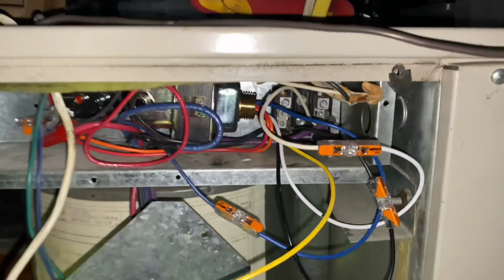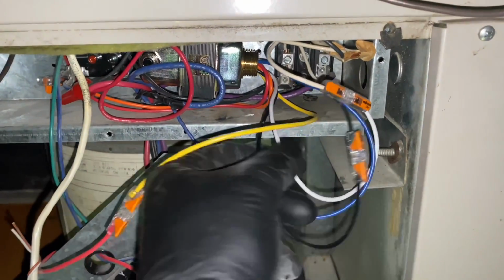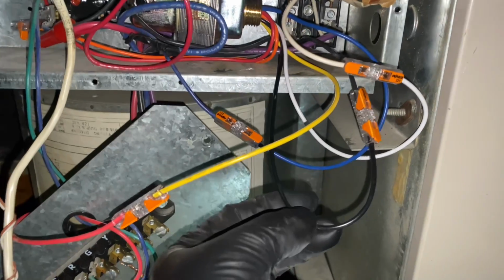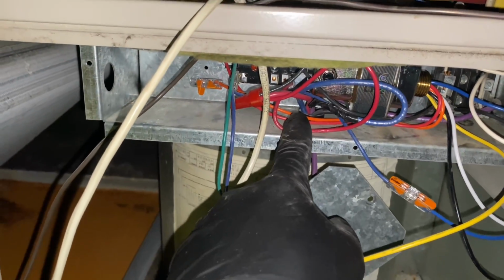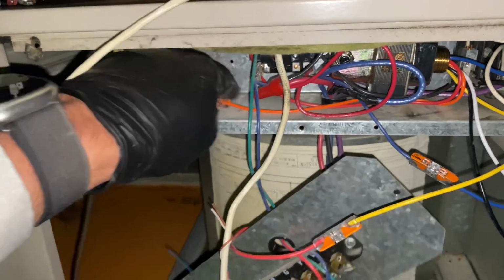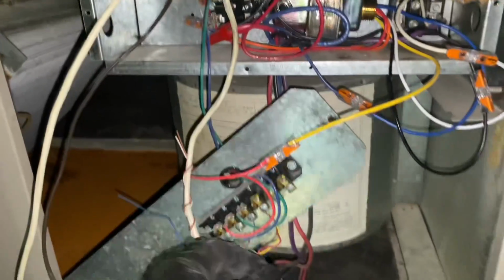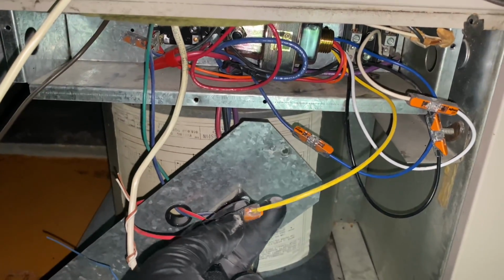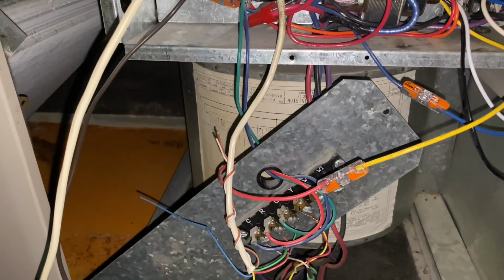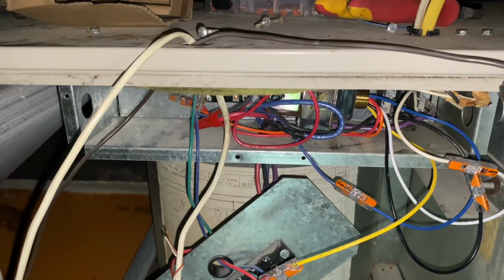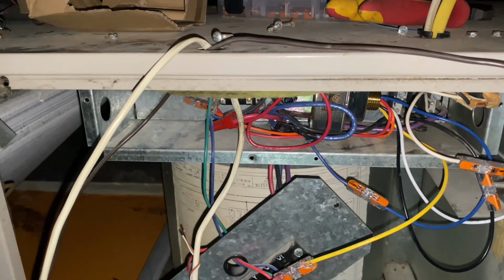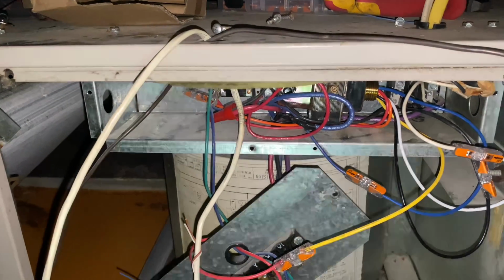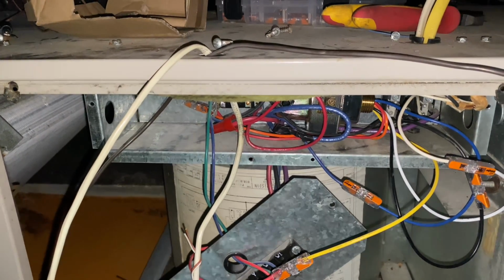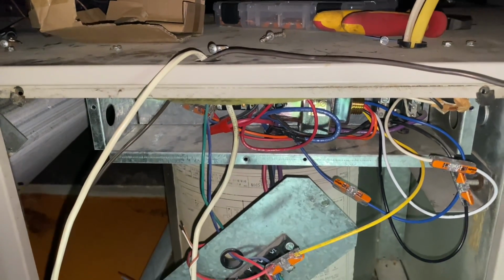So right now I have the black and the white. White is common, black is the line voltage, that's 110 volts. I have my red and my orange, just Wagoed off back there in the corner, right? And I have my 24 volts and my common hooked up to the original circuit. Now, we already checked the coil voltage on the contactor, so we know that's good. Didn't see any other issues here. No shorts, so let's turn the power on.